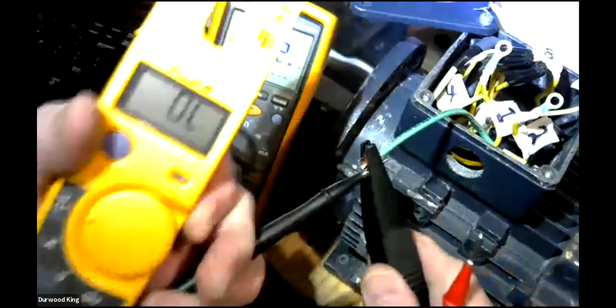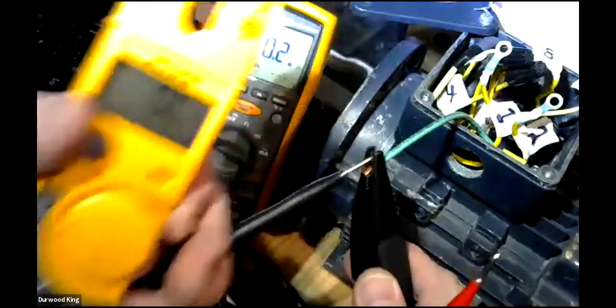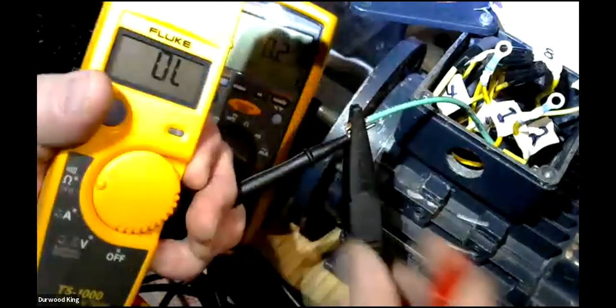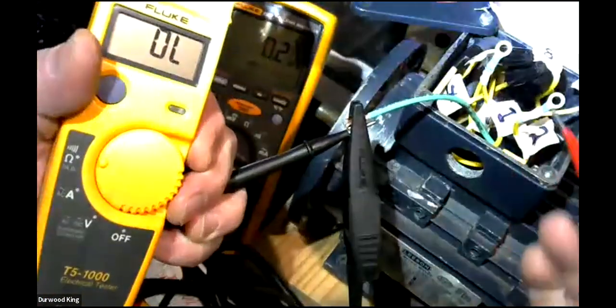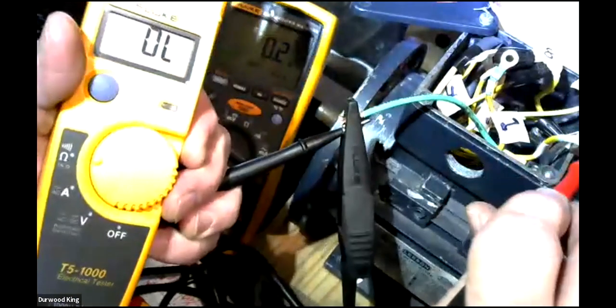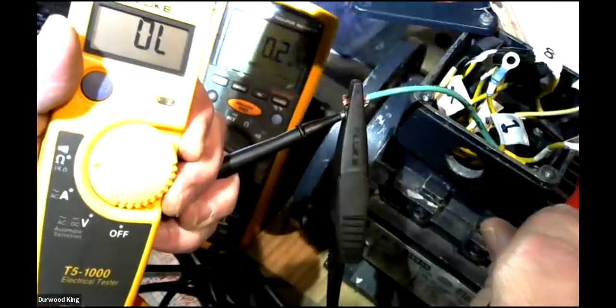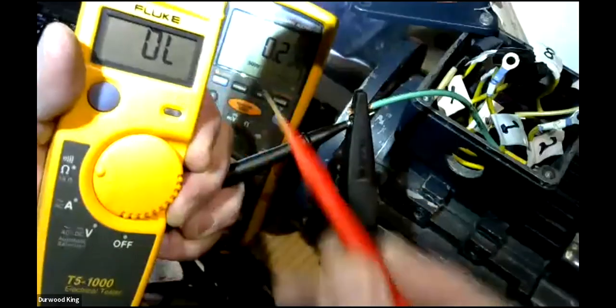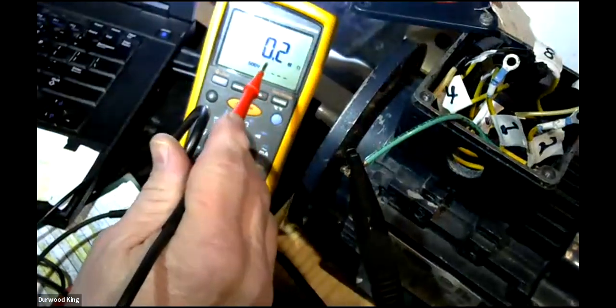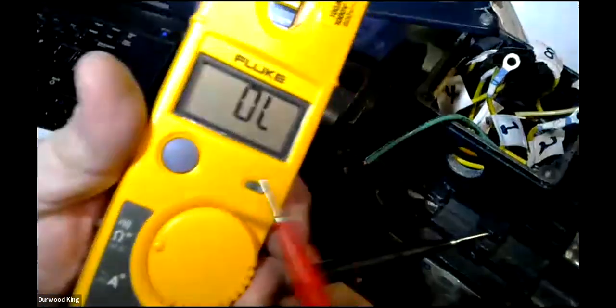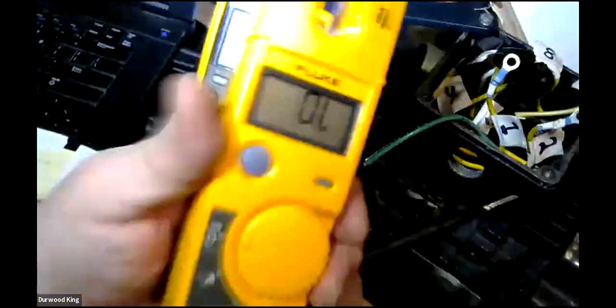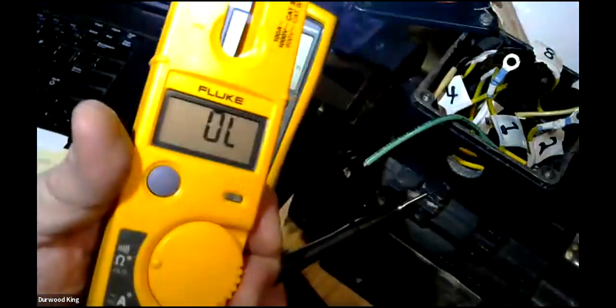So if I go to ground, I go to ground, and then I also go to line 2 there. You see that? It ain't reading it, is it? No. It's not reading it because, look, this meter won't read above 1,000 ohms. This meter will read it in the millions of ohms. That's why this meter is no good for doing what we just did, because you'll think that motor's all right, but that motor's not all right, you know?